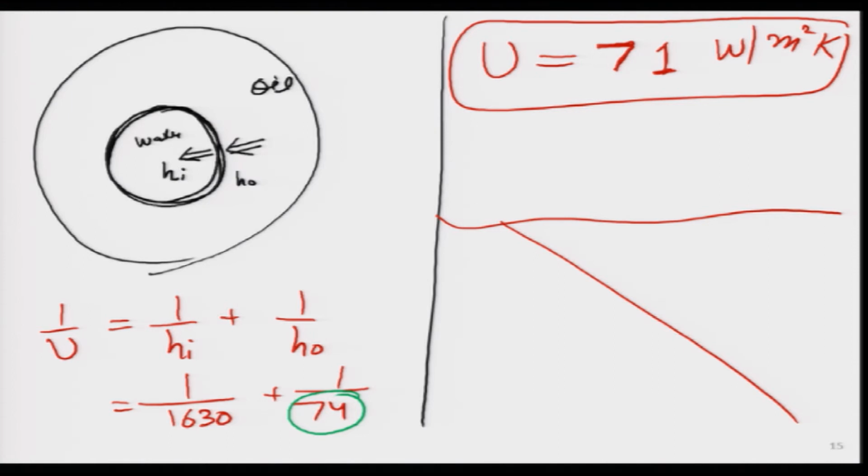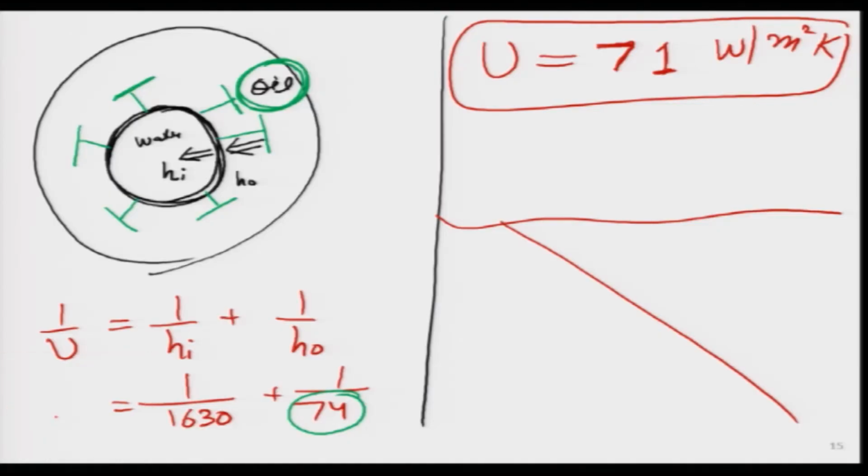Which means this is not part of today's lecture, but in future what engineers would try to do is somehow figure out a way of increasing the area over here, which means I have figured out that on this side of the copper pipe, this oil is having some trouble in transferring the heat. It is just like if we identify the weakest link inside the chain. So, we have figured out which is the weakest link, then we go and try to increase its strength somehow, so that the whole system benefits. So, over here what we are getting is the weakest link is the transfer between oil and the copper pipe.